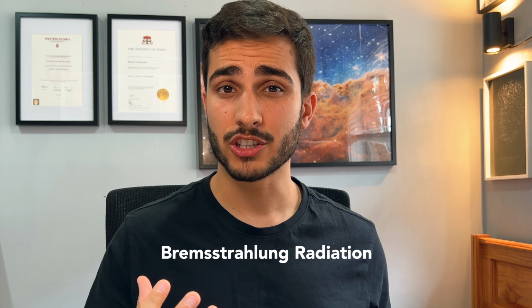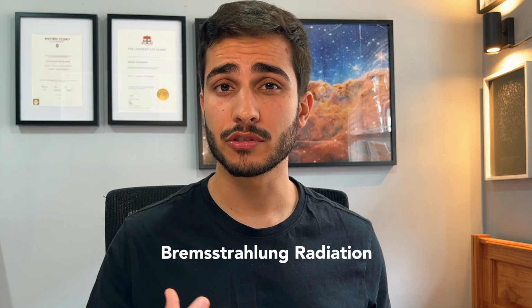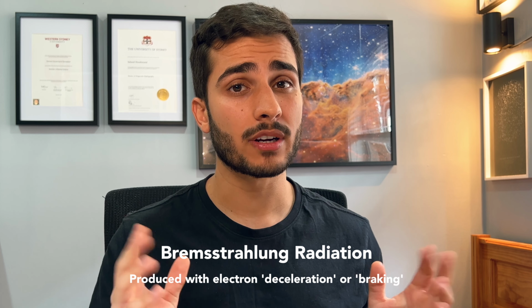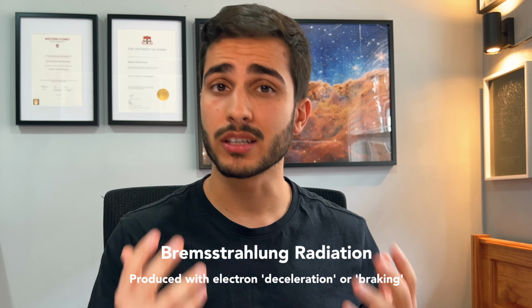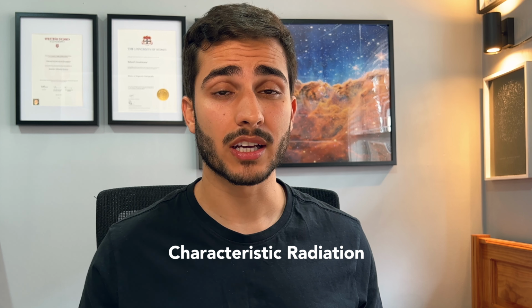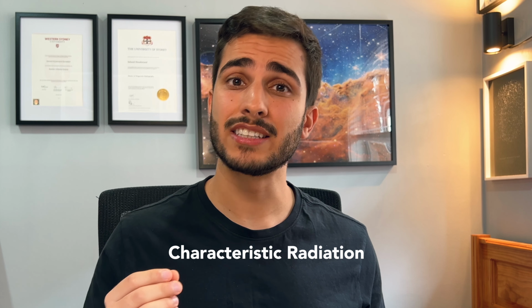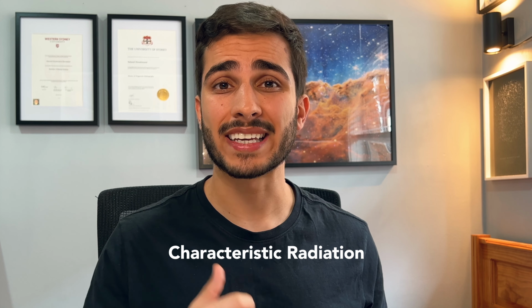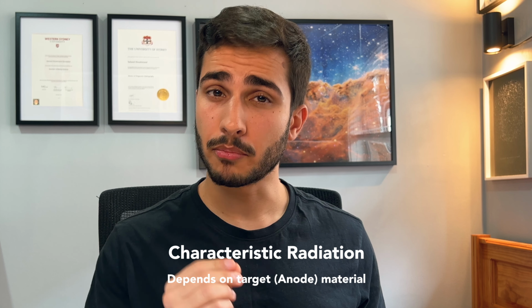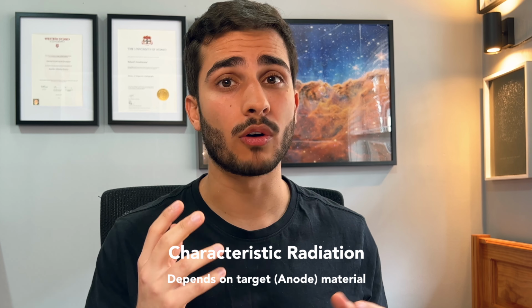So in summary, the difference between these two types of radiation is in their intensity. Bremsstrahlung radiation is typically more intense than characteristic radiation, as it's produced whenever an electron is decelerated, regardless of the material, whereas characteristic radiation is only produced when an electron interacts with an atom and knocks off a K-shell electron, meaning it's dependent upon the atomic structure of the target or anode material.